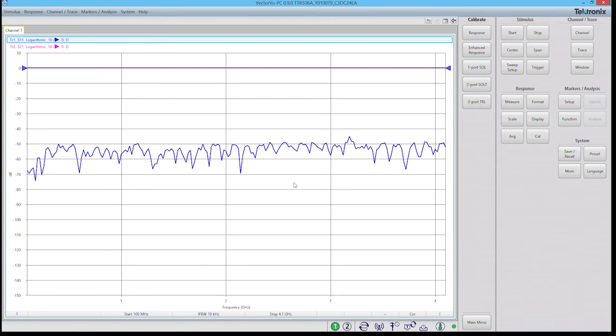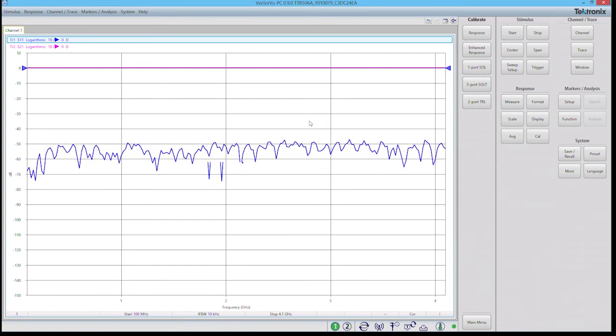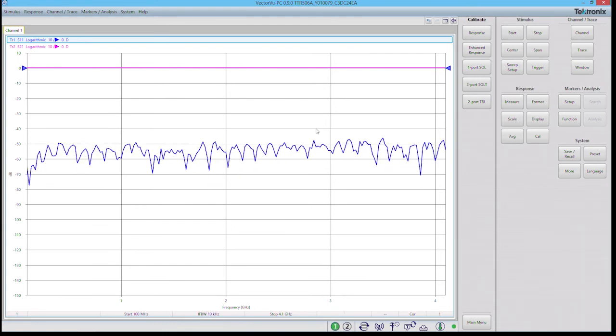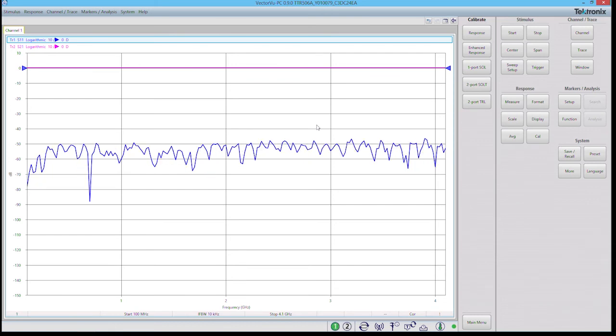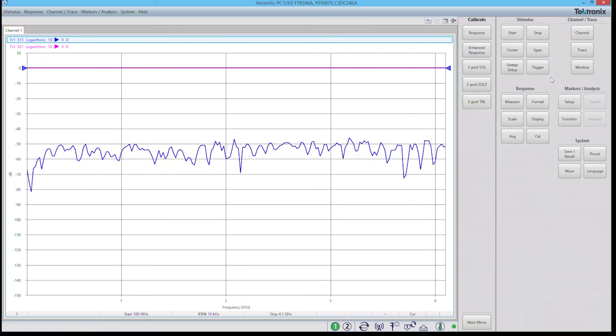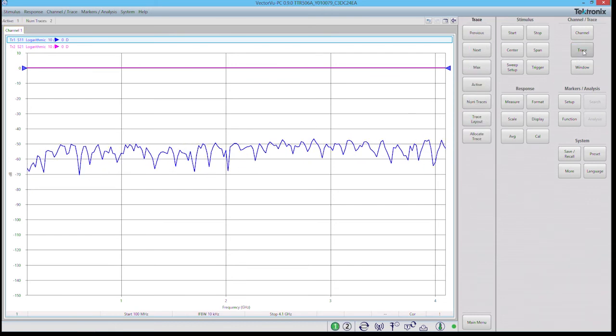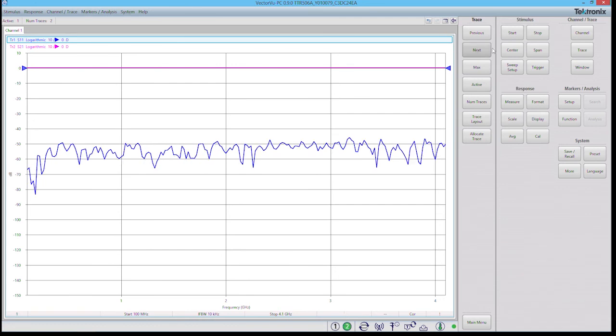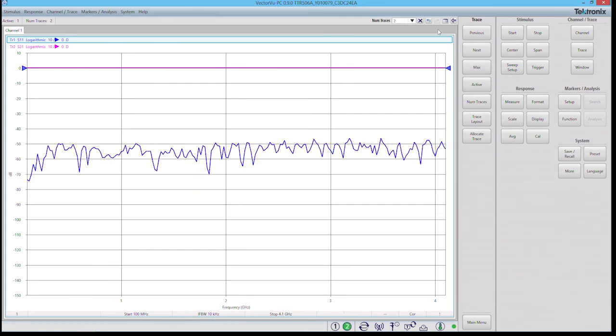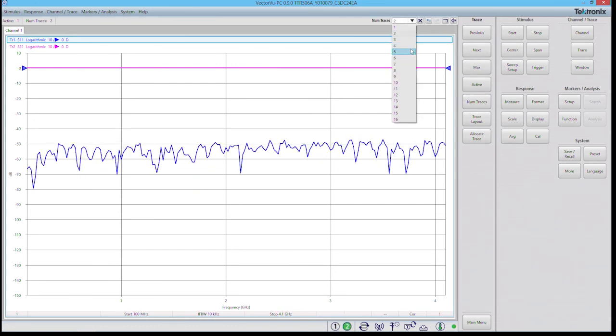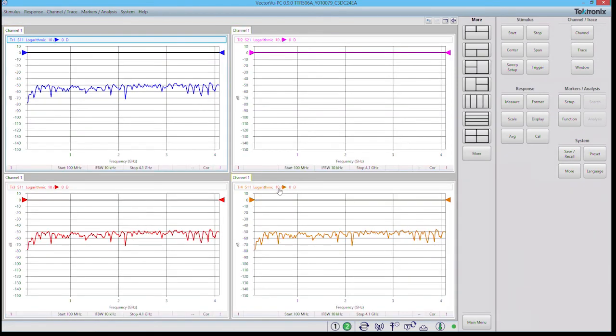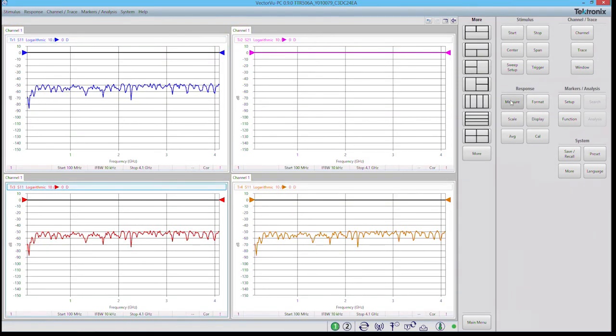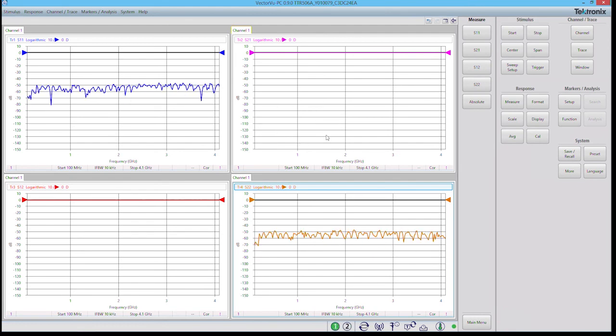Now my device is fully calibrated for both ports 1 and 2. We can check this by looking at all four of our traces and verifying that the response is what we wanted.